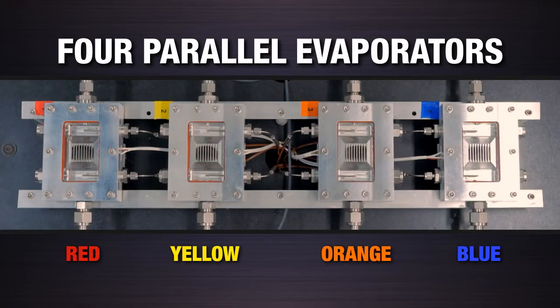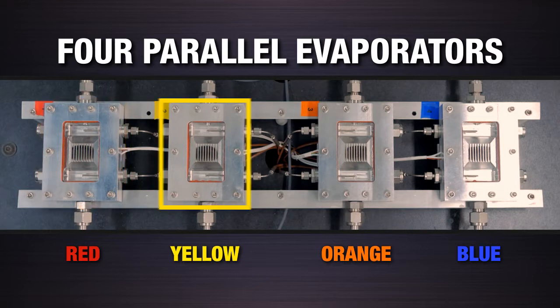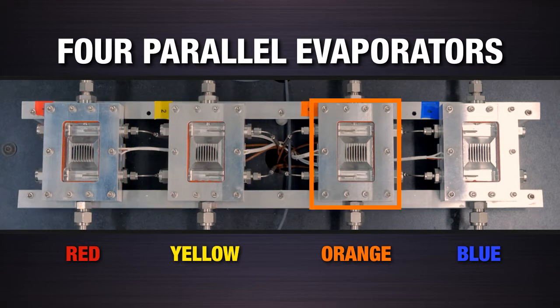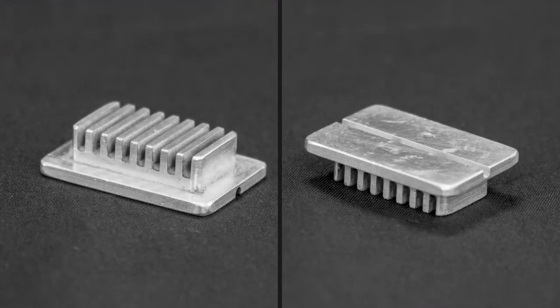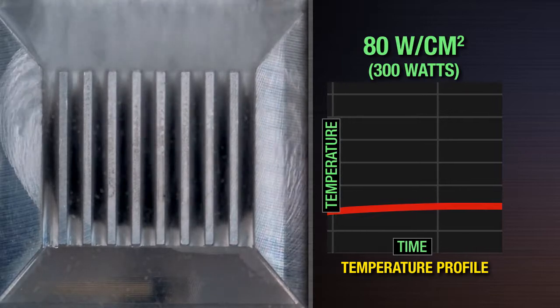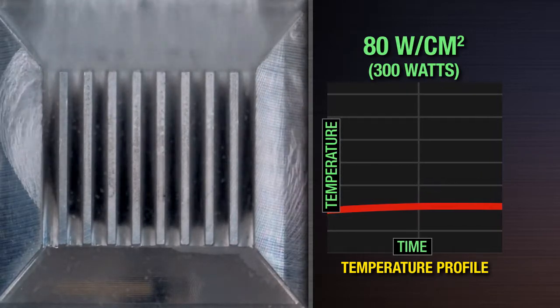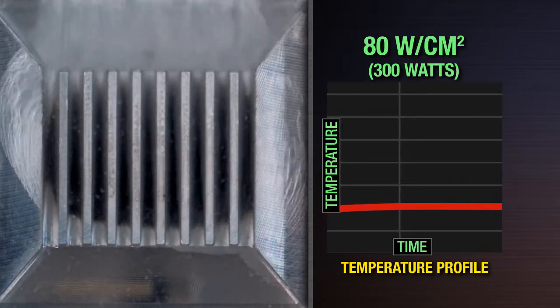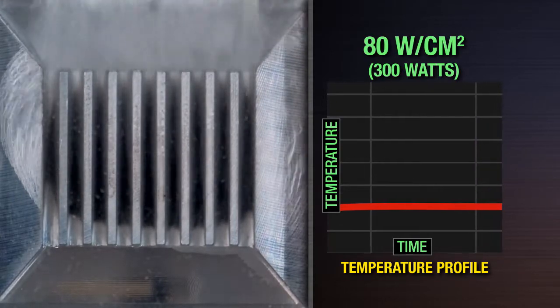Here we see four parallel evaporators, each identified with a specific color, and each with the capability of dissipating different heat loads. Evaporator one is red, two is yellow, three is orange, and four is blue. Here is a sample of one of the evaporators — the hot device is attached on one side, and the fins, which are viewable in the demo unit, are on the other. Under steady state conditions of applying 300 watts to each evaporator at a heat flux of 80 watts per centimeter squared, we can see the incoming liquid begin to boil as it moves across the hot evaporator.